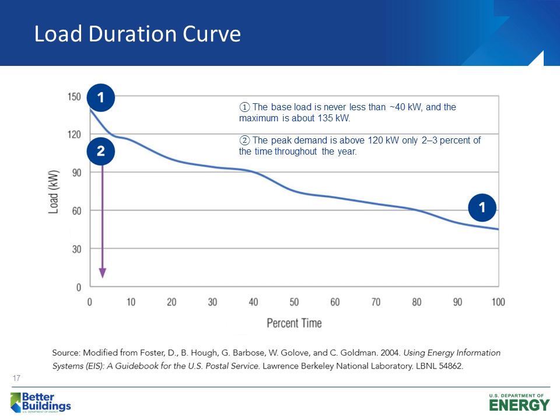We're moving into a little bit on demand. We talk a lot about energy savings and efficiency, but energy information systems can also help manage your demand charges. In this case, you can plot your load duration, showing what percent of the time your whole building is at a particular load. If you have high load for a low number of hours, there's a possibility to reduce that and shave off some of your demand charges.